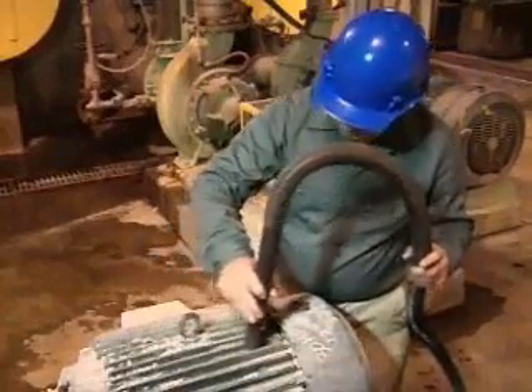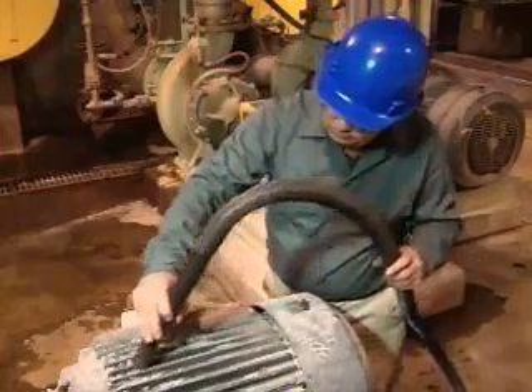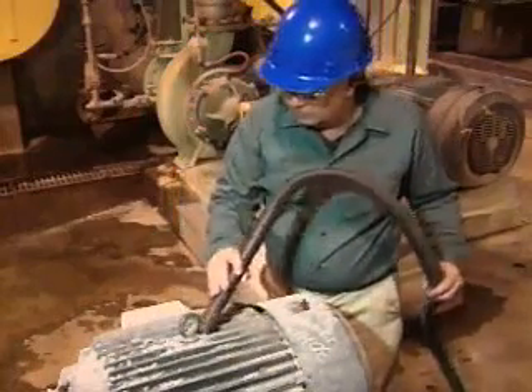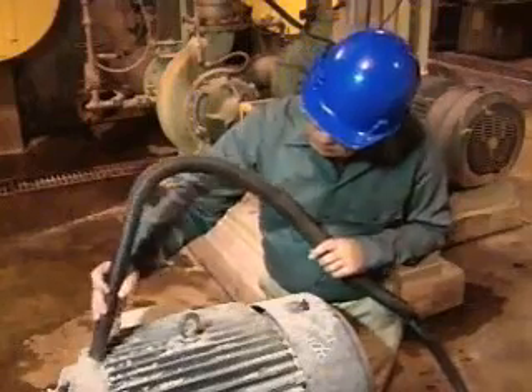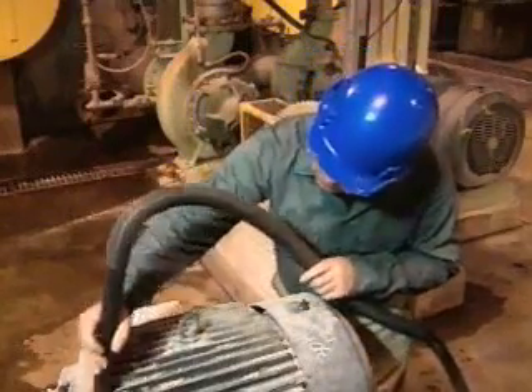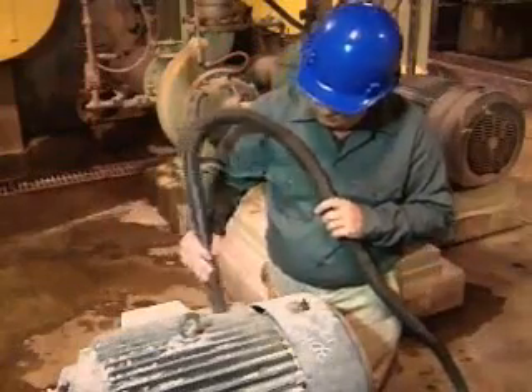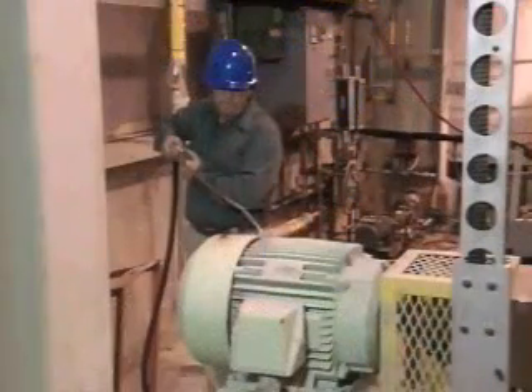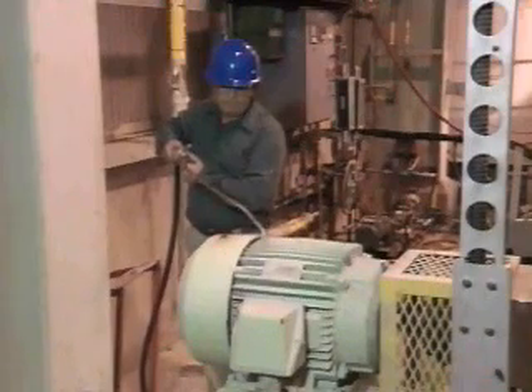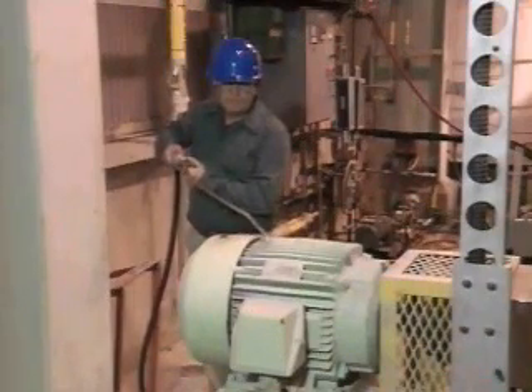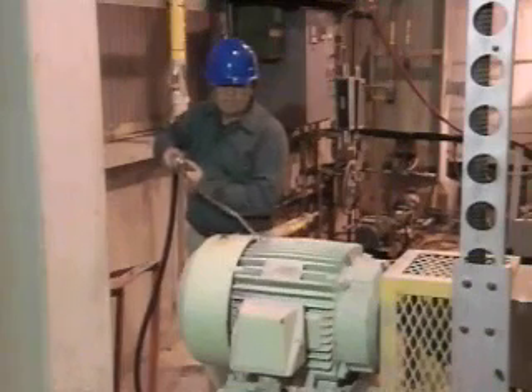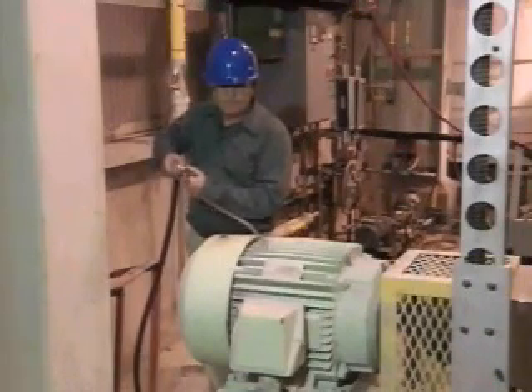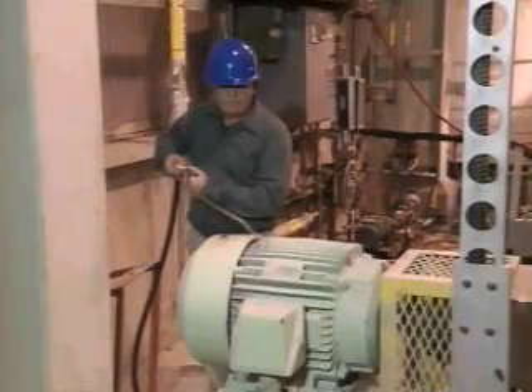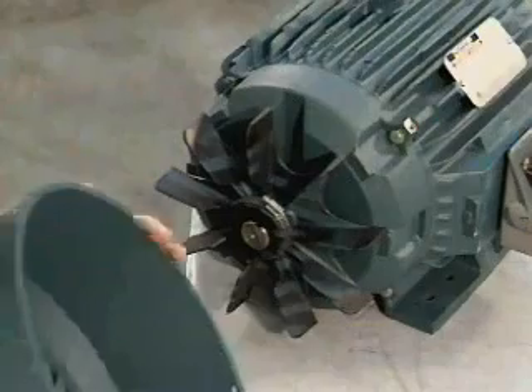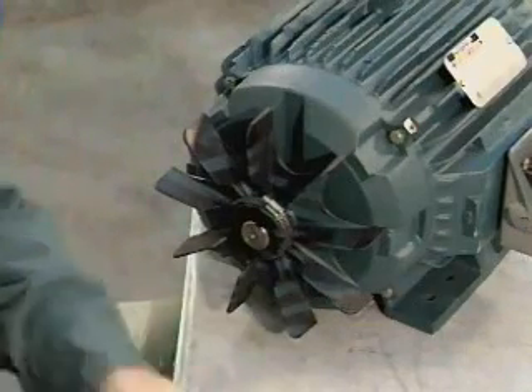Areas that call for cleaning and lubrication should be attended to at once. By taking these routine maintenance actions, you'll ensure continued efficient operation of the equipment. If the motor is not operating, use a vacuum cleaner to clean the exterior of the motor to remove dirt and dust from the vents. If the motor is operating and your facility allows the use of low-pressure air in cleaning, direct the airflow through the motor to remove dust and dirt from the vents. This procedure will keep you away from moving parts during operation. Select Next to continue.